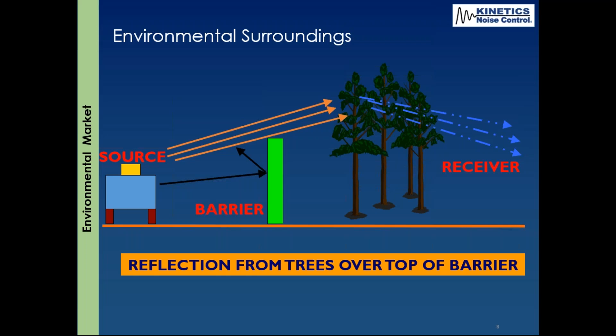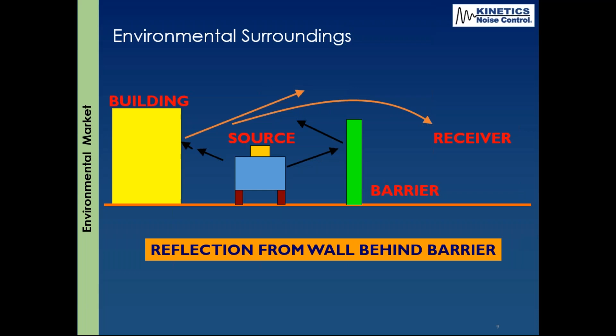Acoustical consultant also looks at noise reflecting over a barrier if there's a building close by. So we may want to use some acoustic products on that building, absorption products, to absorb that reflective noise off the building and up over, all degrading the normal performance of your wall. So the acoustical consultant will take all that into account.